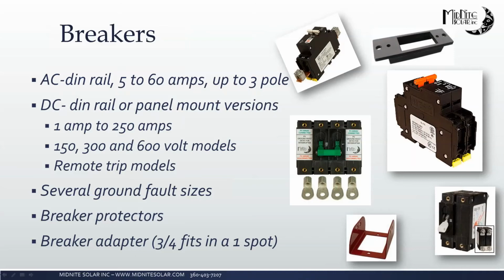We offer a full line of AC and DC breakers, AC DIN rail mount from 5 to 60 amps and up to 3 pole. Our DC are DIN rail or panel mount versions, and rate from 1 amp to 250 amps. We have them available in 150, 300, and 600 volt models, as well as remote trip breakers. And we do offer ground fault breakers in various sizes. Additional accessories that go with those are some breaker protectors, and we also have a breaker adapter that will convert a 3/4 inch breaker to fit into a 1 inch slot.